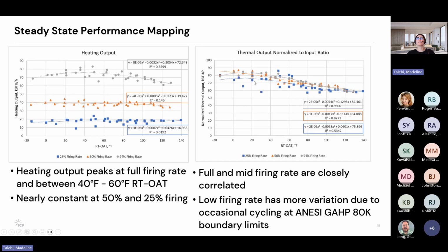So if we normalize that to the corresponding input ratio, we can essentially see how much of an overlap there's going to be, to understand what the overall difference is going to be between the 25% firing, the 50% firing, and that maximum 94% firing. So at the full and mid firing rate, they're closely correlated. The low firing rate is going to have more variation, and it's going to be due to the occasional cycling just at the ANESI GAHP 80K boundary limits. So again, according to those controls and how they're set, you want to be wary, depending on the application, of hovering too low, just because you could essentially hurt your COP or your overall efficiency of the unit if you're hovering at too low of a firing rate.